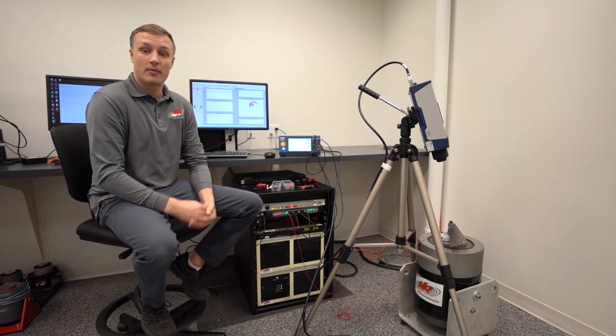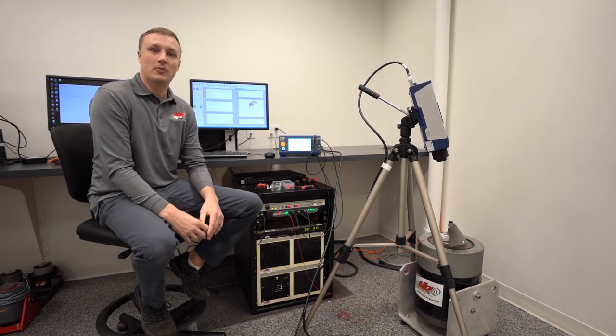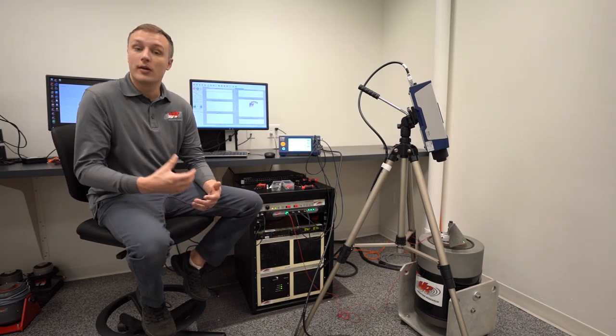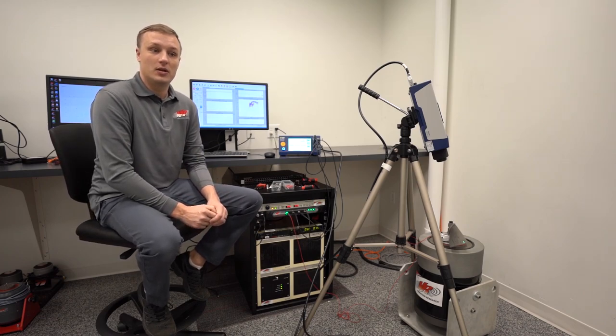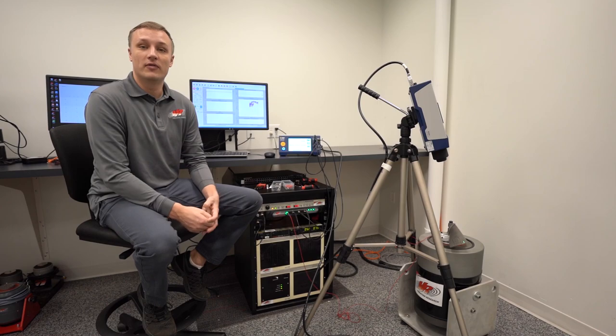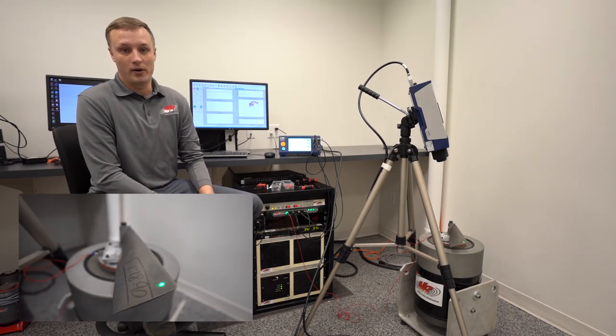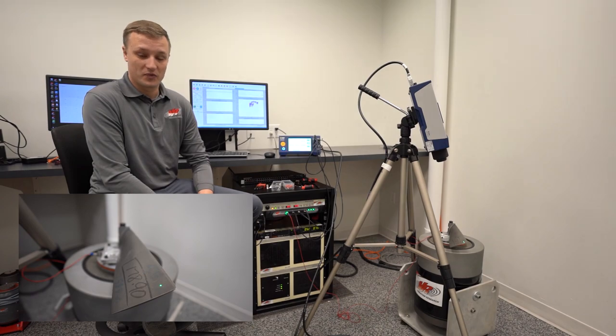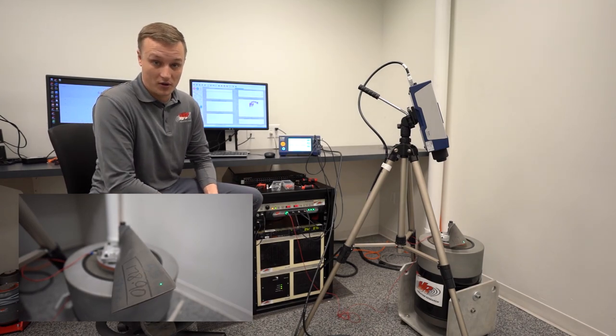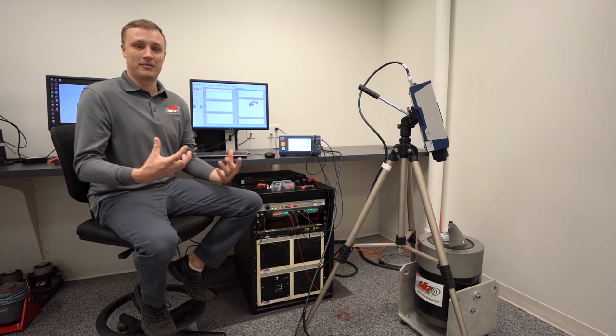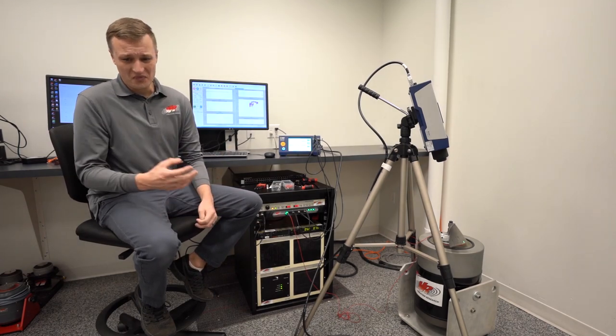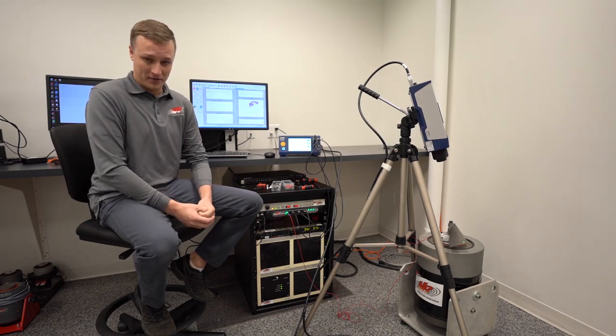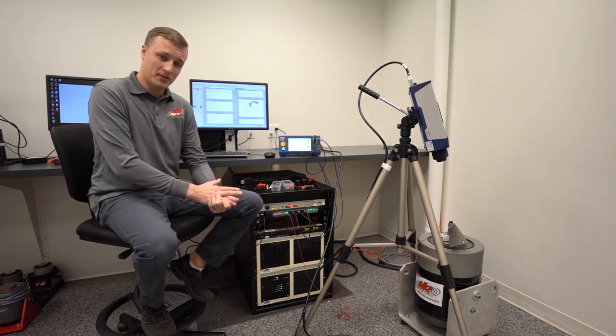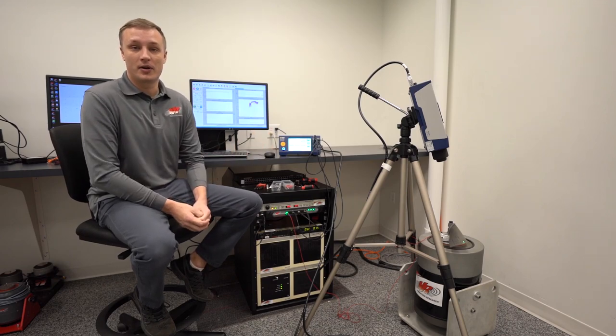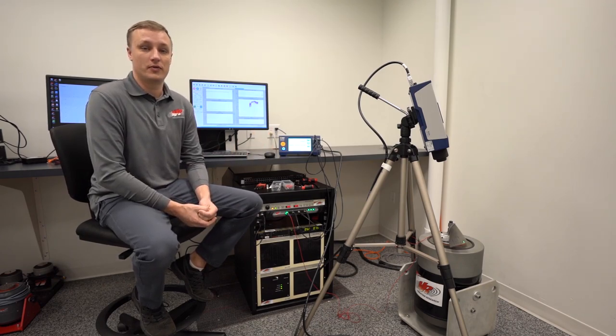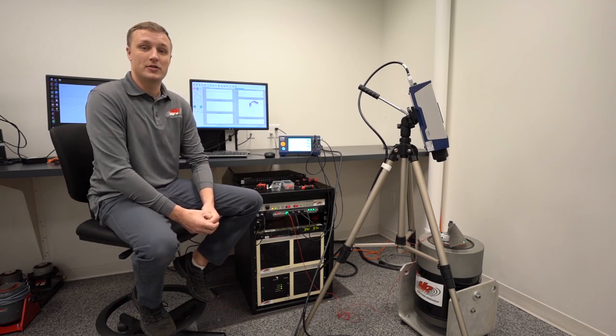You can also use a laser vibrometer for control. It is important to keep in mind that the laser vibrometer, if you are using it for control, has to be protected so that the beam of the laser doesn't get broken or interfered with while trying to run a test. So there may be some safety concerns there, but the fact is, in order to connect and run the software, it is relatively simple. You power on the laser vibrometer, set up your inputs in both the laser vibrometer control software and in VibrationVIEW, and run your test. There is no magic to it.